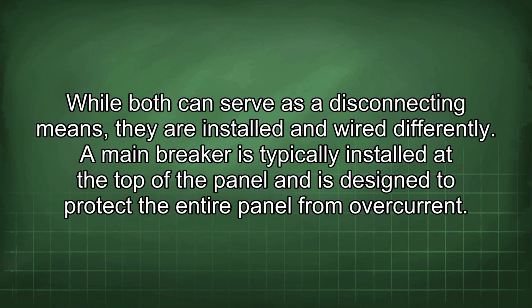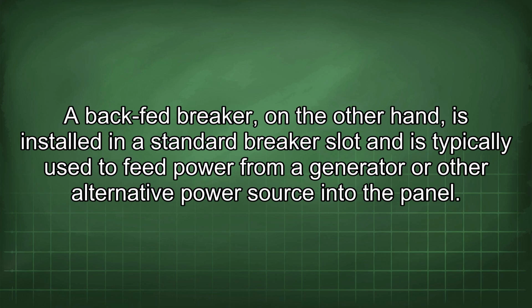While both can serve as a disconnecting means, they are installed and wired differently. A main breaker is typically installed at the top of the panel and is designed to protect the entire panel from overcurrent. A back-fed breaker, on the other hand, is installed in a standard breaker slot and is typically used to feed power from a generator or other alternative power source into the panel.